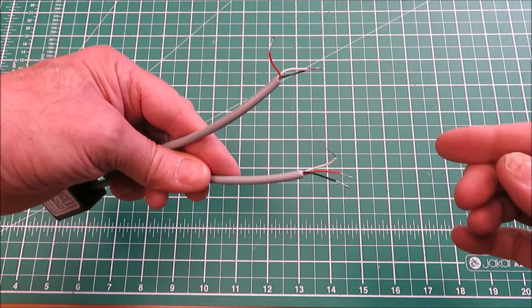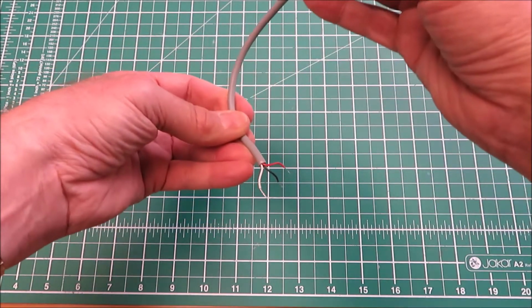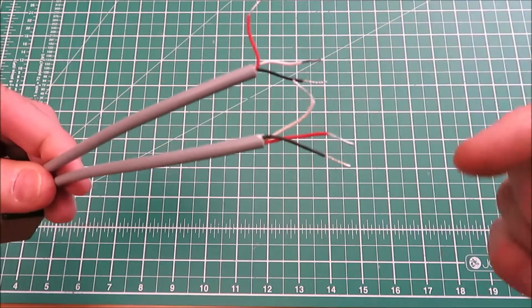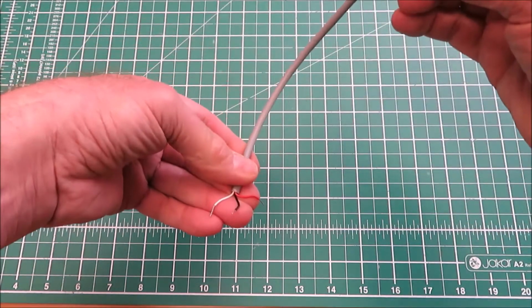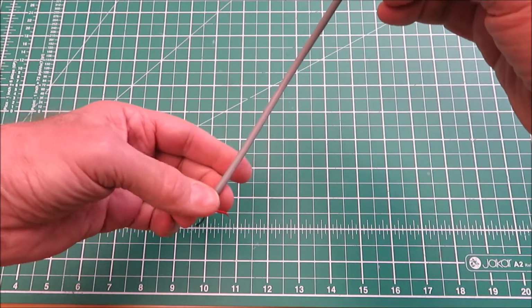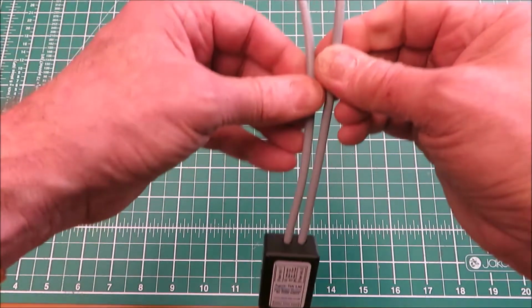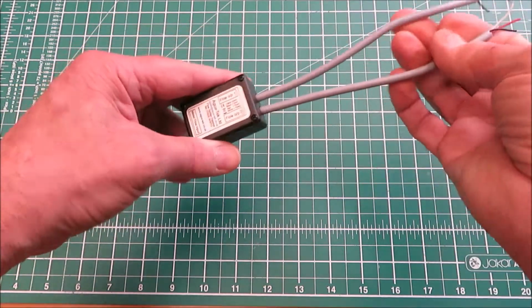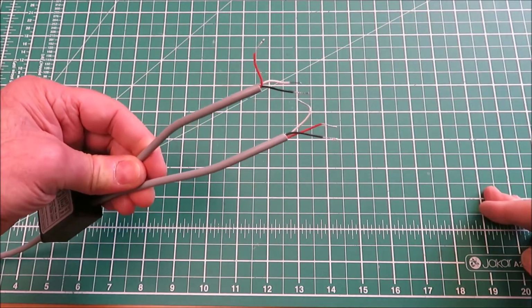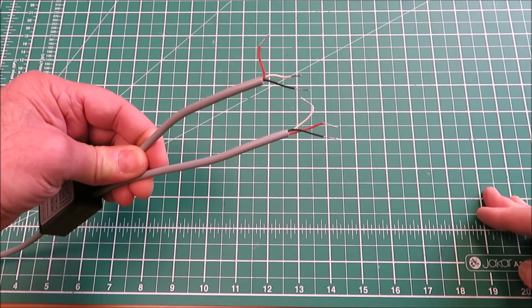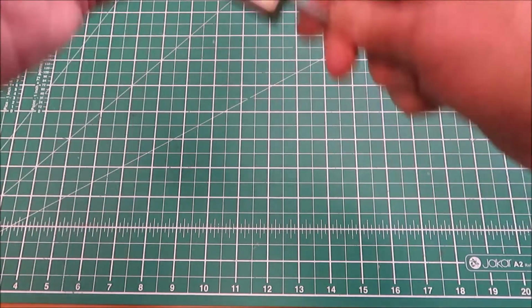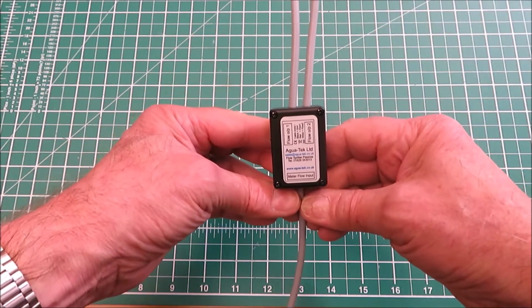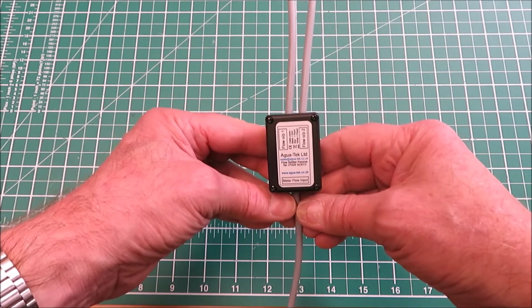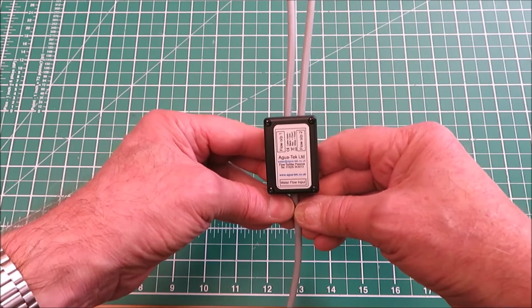The 2 reds are the same channel of flow as the red on the input, and the white outputs are the same as the white on the input, so it just shares either one of those flows to those 2 separate output cables. The black wire is electrically connected to all the other black wires, but the red and white wires have some isolation. This particular unit is useful for using with data loggers, but not building management systems. The higher voltage sometimes causes a problem, so that's when you would use the electronic splitter.